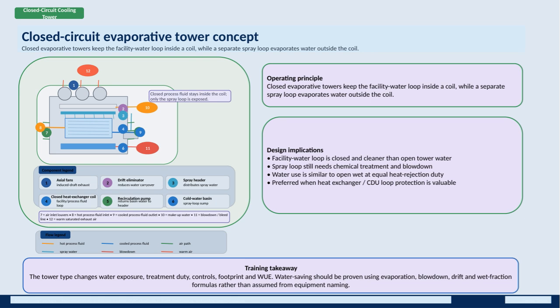It's important not to assume water savings just based on equipment labels, but to calculate them using detailed factors like evaporation, blowdown, drift, and wet fraction formulas. Looking at the components, axial fans create the induced draft to move air through the tower, while drift eliminators reduce water carryover. Spray headers distribute water uniformly, and the closed heat exchanger coil keeps the process fluid contained. A recirculation pump returns water from the cold water basin back to the spray headers.